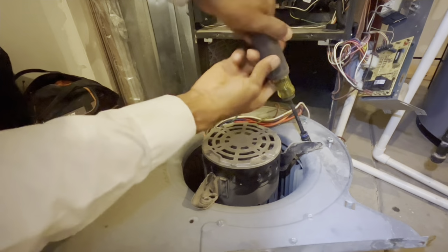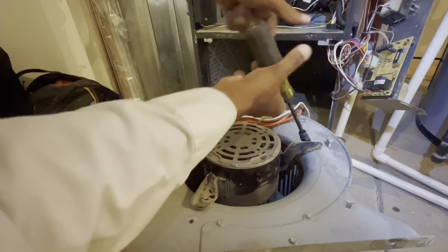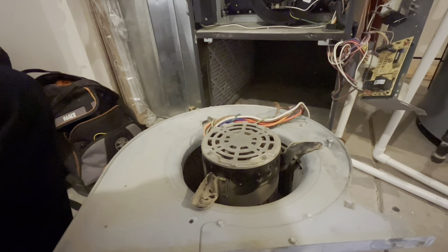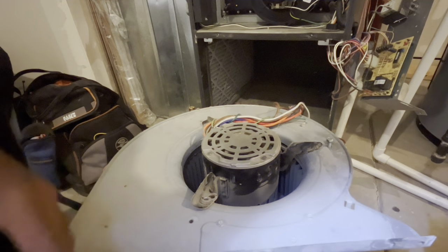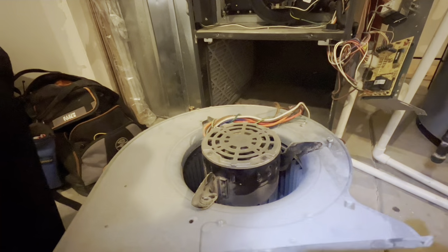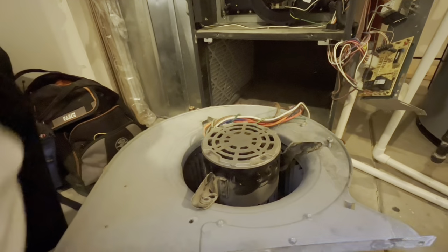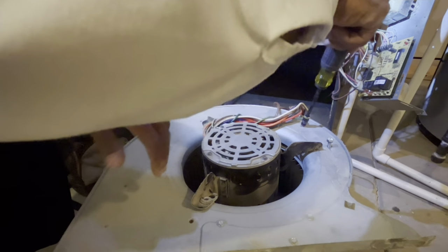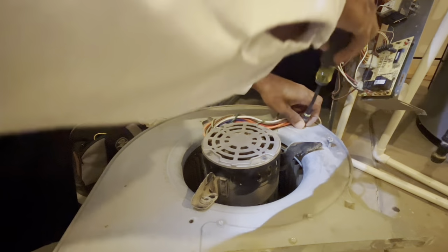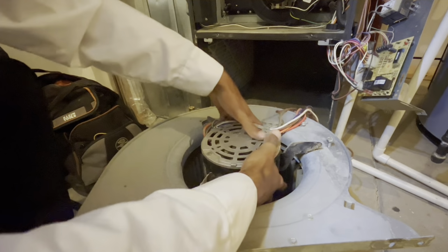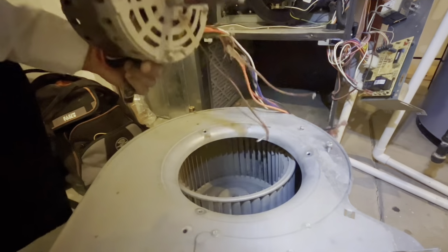All right, well, there's 3/8 inch bolts actually holding that PSC permanent split capacitor motor in place. Basically it's a bracket that's welded onto these factory motors. So if you were going to replace this motor with a universal motor or something that you buy online, you have to make sure that you get what's called a 3-arm bracket. So it would be the motor, the bracket, and then you want to replace the capacitor at the same time.